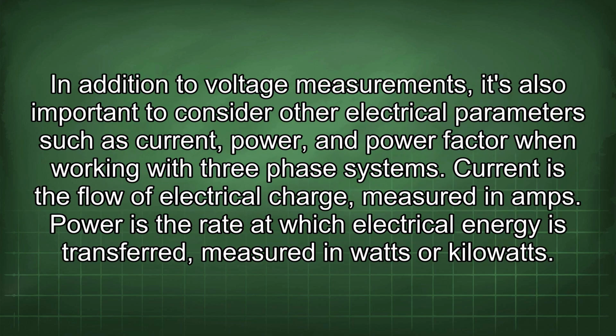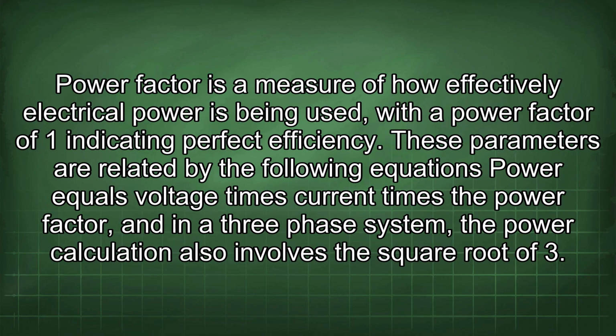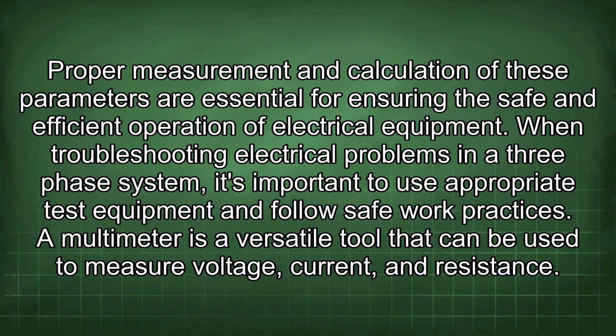In addition to voltage measurements, it's also important to consider other electrical parameters such as current, power, and power factor when working with three-phase systems. Current is the flow of electrical charge, measured in amps. Power is the rate at which electrical energy is transferred, measured in watts or kilowatts. Power factor is a measure of how effectively electrical power is being used, with a power factor of 1 indicating perfect efficiency. These parameters are related by the following equations: power equals voltage times current times the power factor. And in a three-phase system, the power calculation also involves the square root of 3. Proper measurement and calculation of these parameters are essential for ensuring the safe and efficient operation of electrical equipment.